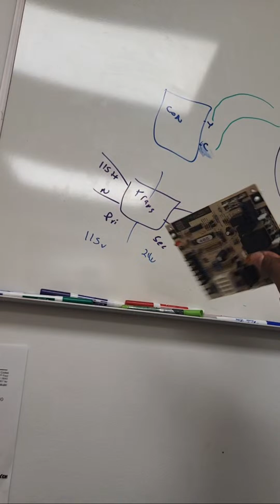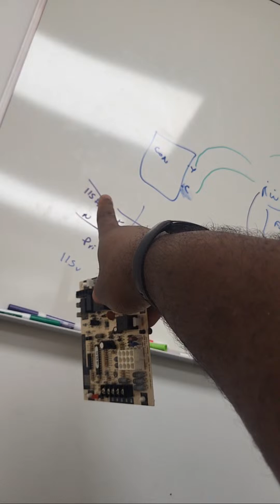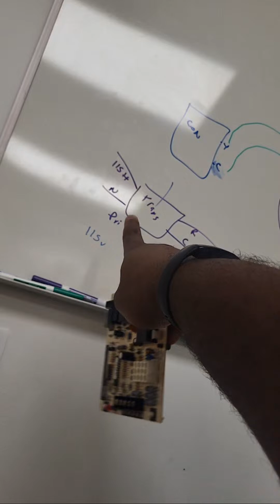So think about it like this: your circuit board gives power to the primary side of your transformer. The transformer is saying, hey circuit board, I need 115. Your circuit board says, okay, I'm going to send 115 from my X-former side to your primary. Power goes in from one side, and the transformer says, okay circuit board, you sent me 115 from your transformer terminal. Now if I'm working fine, I'll step that 115 volts down to 24. And as a result, remember those two R to C terminals? That transformer is now going to send 24 volts between R and C.